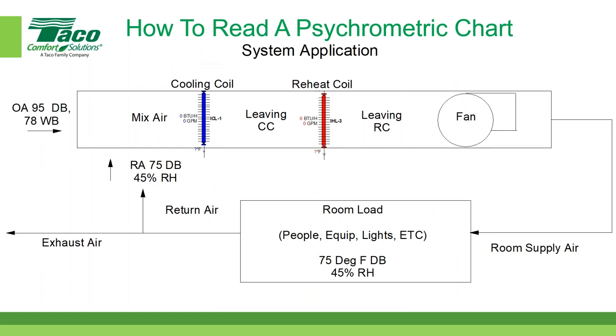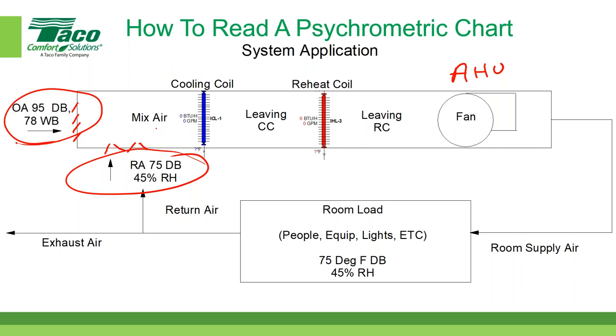So here we have a more detailed system application. We're using some of the characteristics that we had before. Now we have a more detailed air handling unit here, so let's label this air handling unit. Let's say it has an outside air louver. There's our outside air source. And it has a return air damper. And then the return air, we said 75 and 45% relative humidity. The outside air is 95 dry bulb, 78 wet bulb, and they're going to mix. That mix calculation is the one we just showed you.